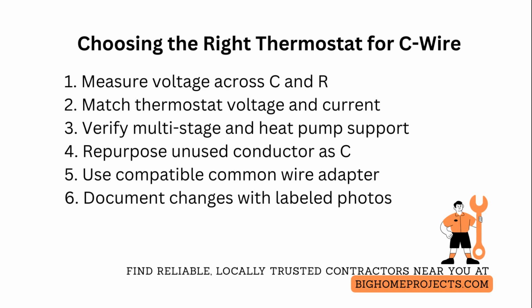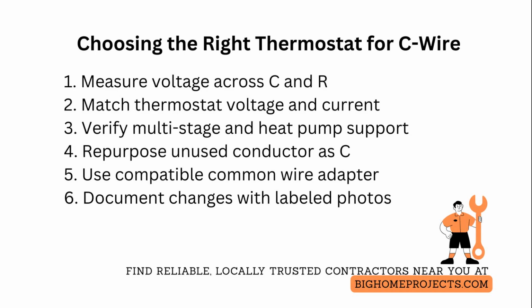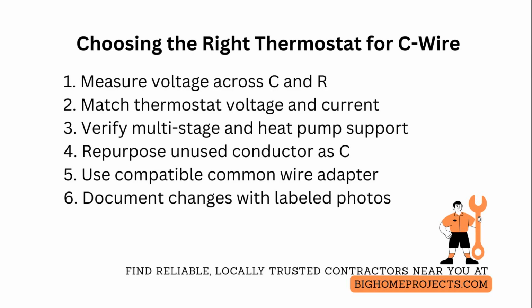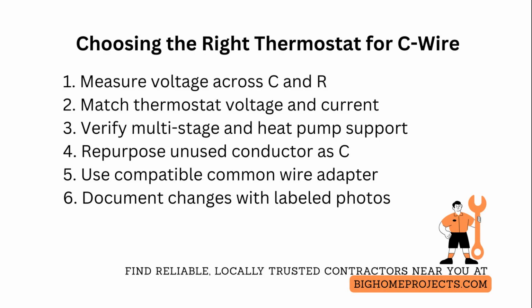Match the thermostat's input voltage range and current draw. Smart thermostats often list minimum milliampere draw, so pick one that the transformer can reliably supply without tripping the furnace control board. If not, get a separate 24-volt power adapter or an adapter kit rated for your system.